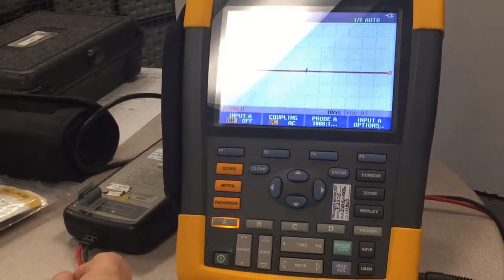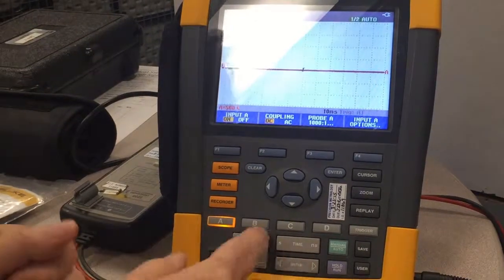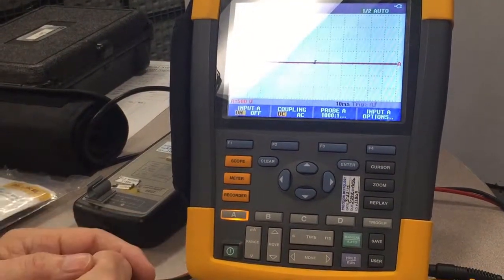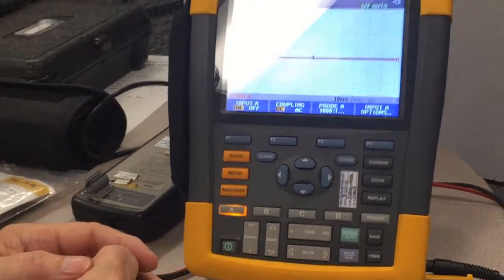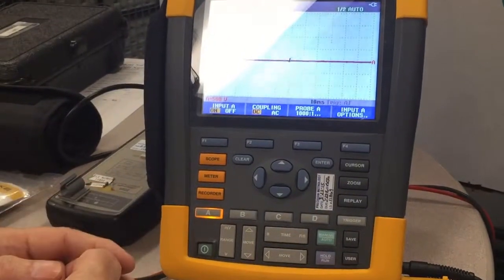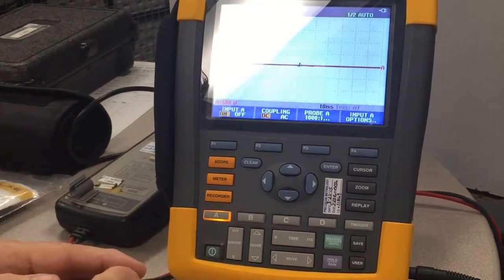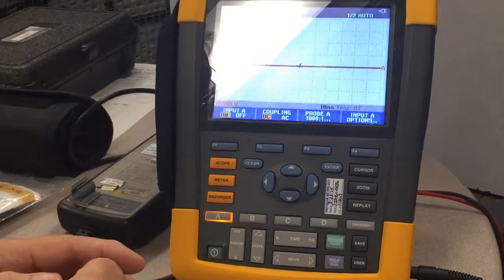The next thing we're going to do is we're going to set our time base. In this demo, we're going to be looking at the output of the drive when it's running 60 hertz. The 60 hertz period is about 16 milliseconds. I like to start out with looking at approximately two cycles. That would be 32 milliseconds.